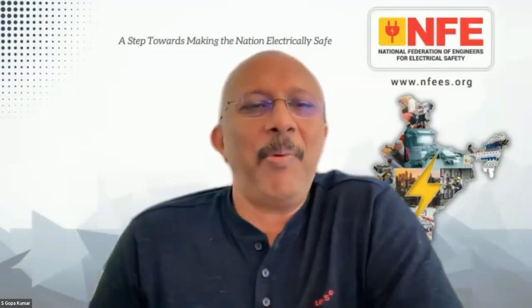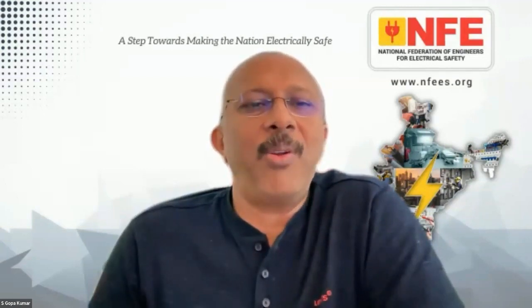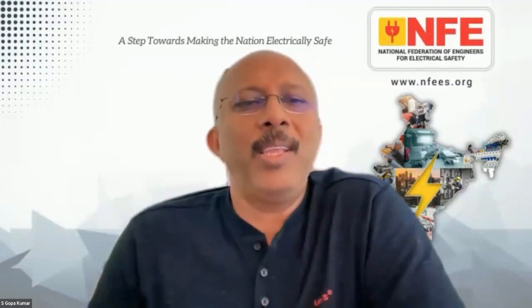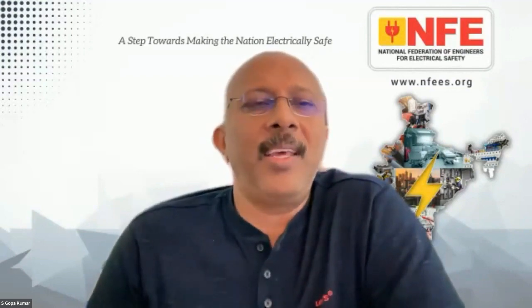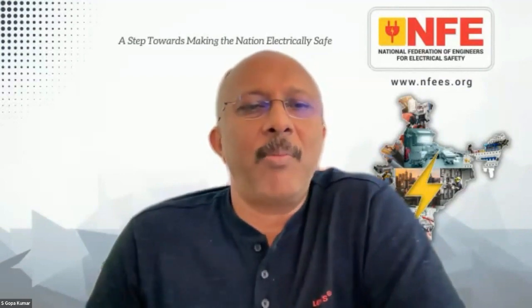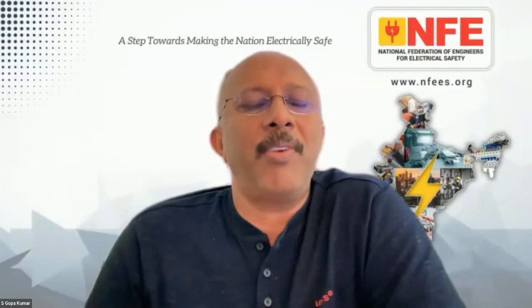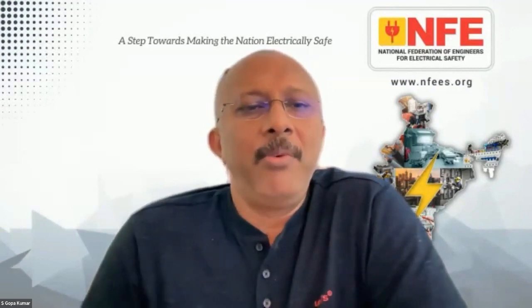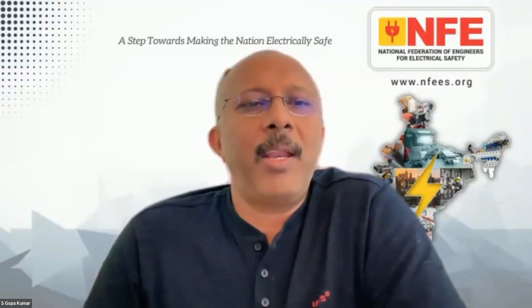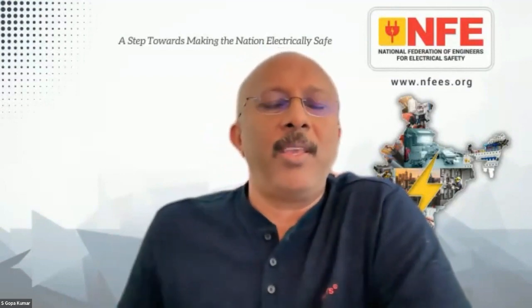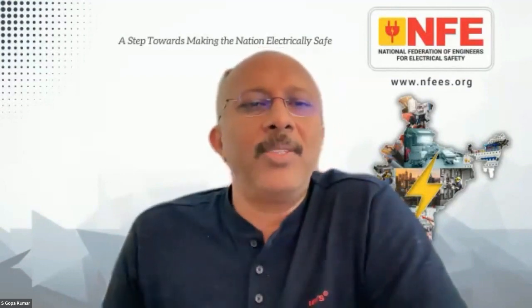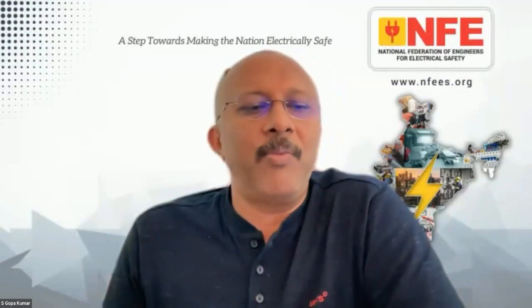Yeah. See, one of the problems which we face all over India is whenever there is a fault on the HT side of the transformer, mostly the low voltage system is TT, and whenever there is a fault on the HT side of the transformer, the connected equipment on the low voltage side is failing. And in my view, the discom has to be penalized, because we are paying for electricity and we are taking their troubles into our house and our equipment is burning. Unfortunately, the legal system has to be improved, and I'm sure it will happen soon. Yes, totally agree. I think the same in England, that the electricity companies should be held to account far more clearly by the governments, without a doubt.